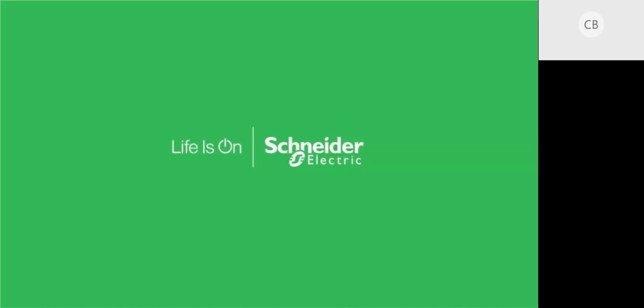Okay, thanks, Karsten. Is cloud data accessible via API? I assume that question relates to the Microgrid Advisor software. The answer is yes. We have standard APIs available in order to communicate to this, and specifically when you think about energy peak demand shaving, perhaps we have an energy storage system attached to our UPS, and Mark explained where we take partial energy from the utility and partial from our batteries, to discharge them to support our load. This may in itself not be sufficient to make it an attractive, long enough, powerful enough kind of event to participate in peak demand shaving.